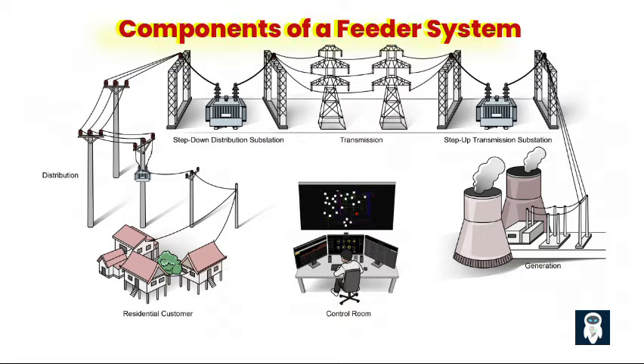Fifth, switching devices such as switches and disconnectors are used in the feeder system to control the flow of electricity, allowing for manual or automated switching of circuits to enable maintenance activities, load balancing, and rerouting of power during outages or system upgrades. Sixth, voltage regulation devices such as voltage regulators and capacitor banks are employed along the feeder system to maintain voltage levels within acceptable limits, compensating for voltage drop due to the resistance and impedance of the feeder lines.